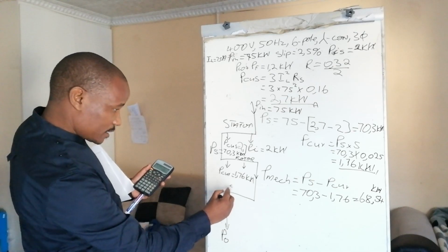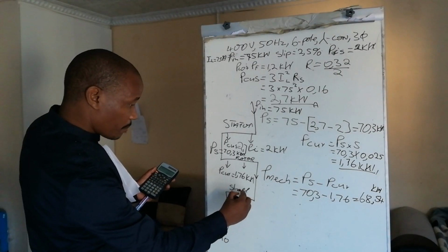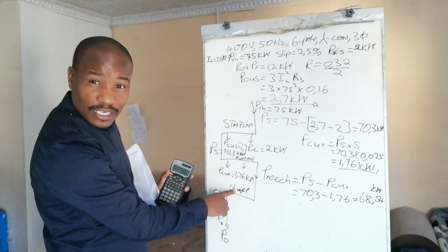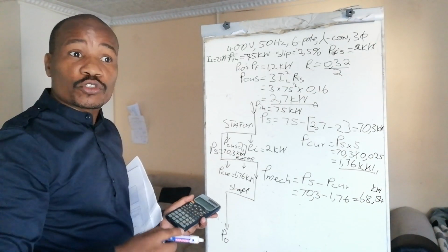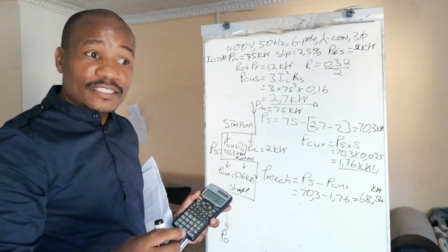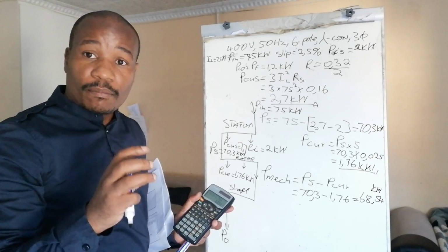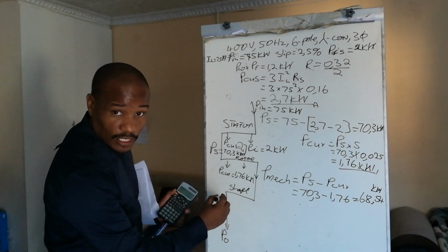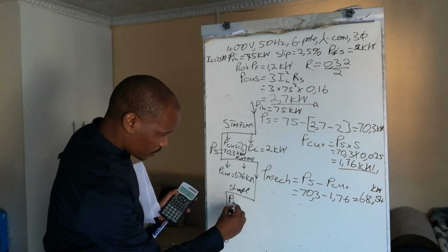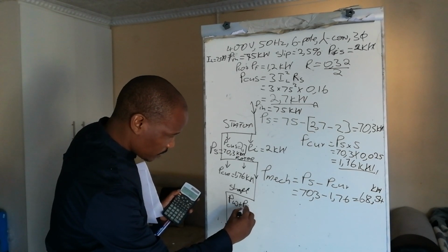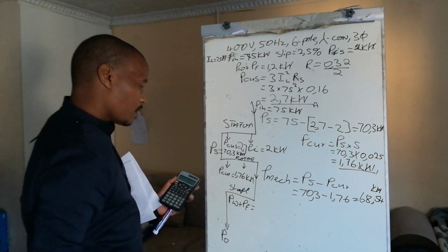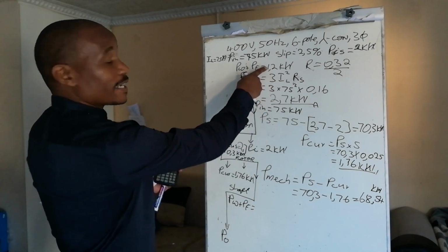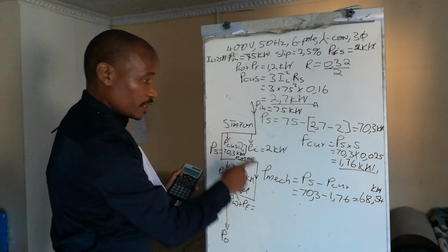But we are given what? This is the shaft part, if you remember well. And the shaft part consists of the rotational losses. The rotational losses normally are due to the fan that is installed at the back of the motor and is mounted on the rotor. They consist of the windage plus the frictional losses, and they are given as 1.2.